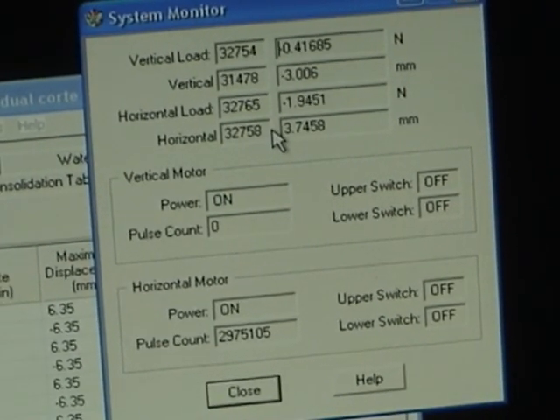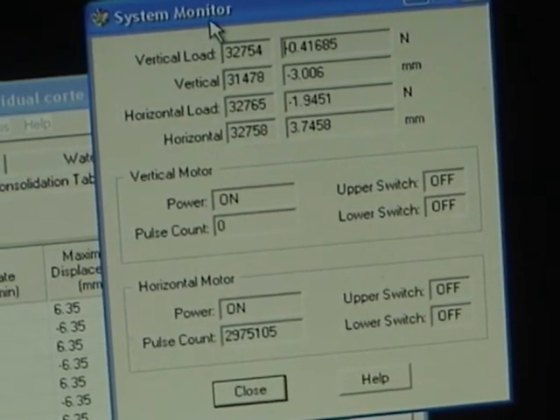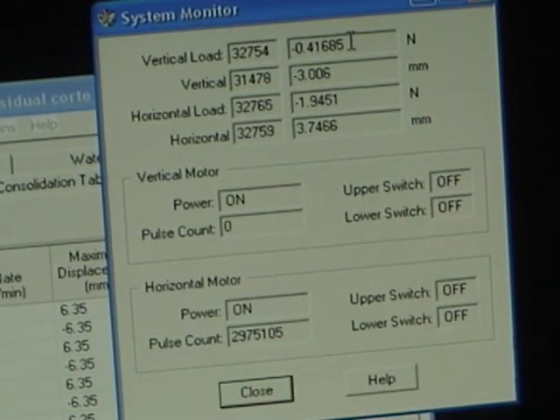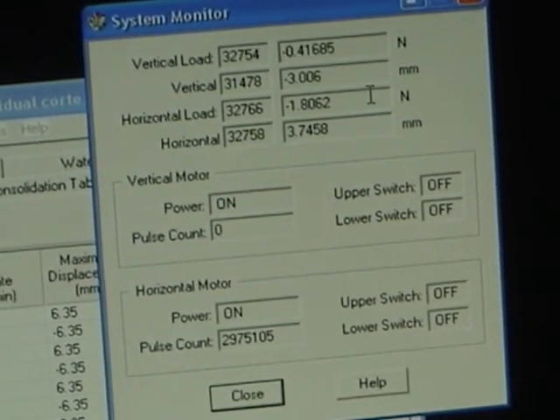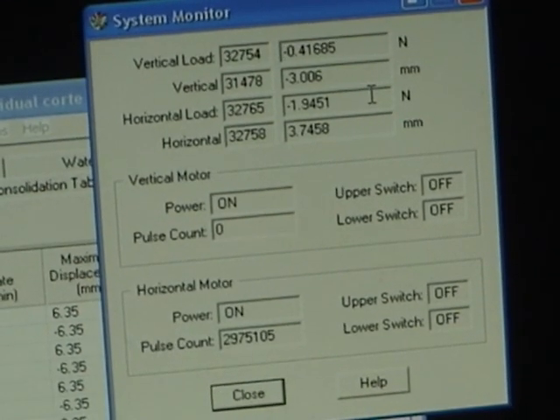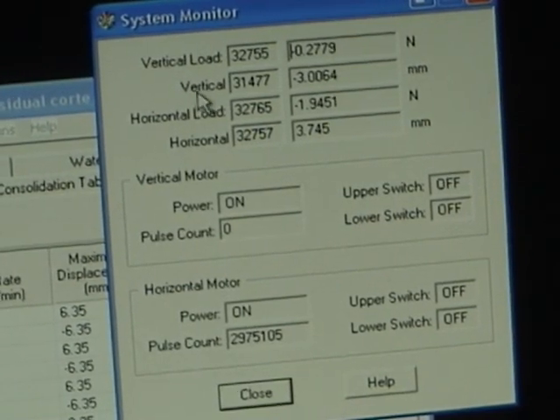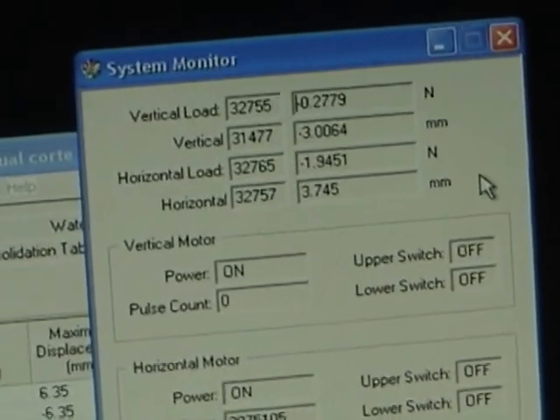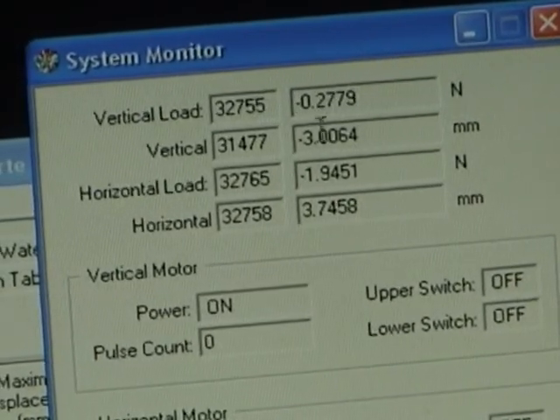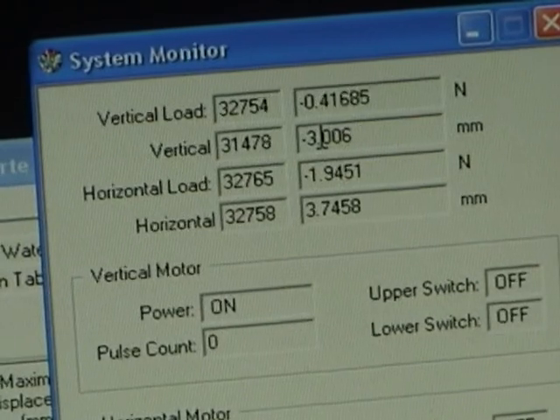Now the values that you see here you can check manually to confirm they are correct. You can press on the vertical load cell and you should see about 100 Newtons. You can also press on the horizontal load and see about 100 Newtons by hand — that's how much a human being can press. You can also check the vertical displacement and horizontal displacement by inserting a gauge with a known thickness and verifying the change in displacement equals that known thickness. This is good to go — the test is ready to run.